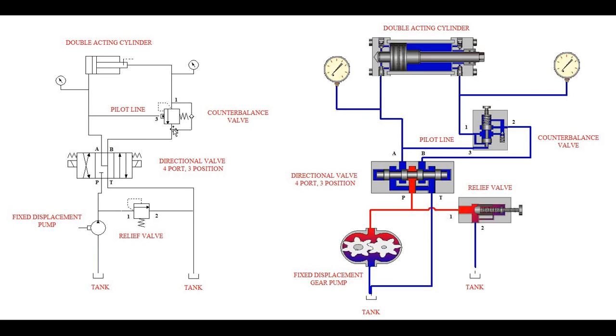What is the counterbalance valve? Counterbalance valve's job is to manage pressures and flows coming from overrunning loads. What you have to envision, and it's not depicted here, is something trying to pull the cylinder out, make it extend, some kind of a load on the rod. Maybe if it was mounted a certain way, it could be a gravitational type load, depending on how it's oriented.